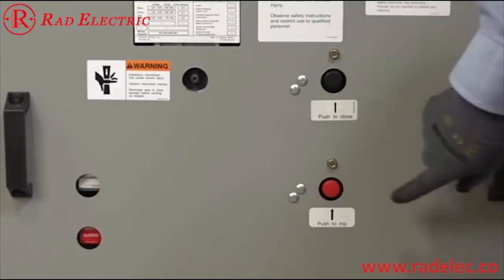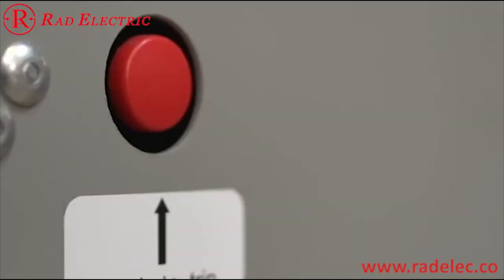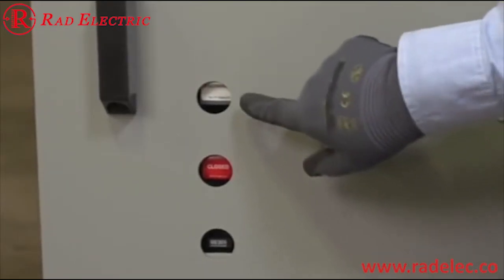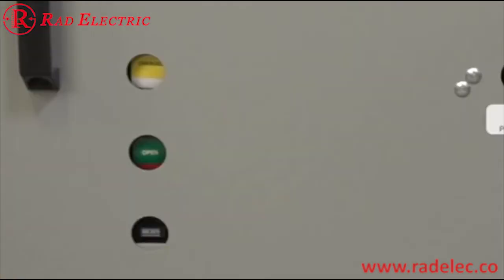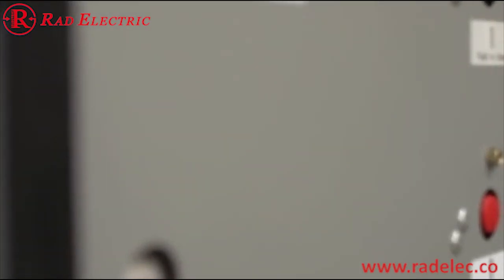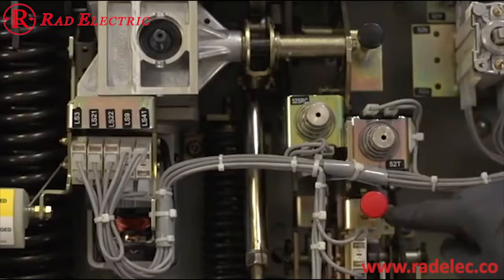This is where the charging handle is connected to charge the closing springs in the circuit breaker. These are the push to close and push to trip buttons. Both are colored according to ANSI standards. On the left side of this panel is the spring charge status indicator, which is either charged or discharged. Here is the operations counter for the circuit breaker. Remember, Siemens medium voltage circuit breakers are tested in the factory, so it's normal for a brand new circuit breaker to show 250 to 300 operations on this counter. And finally, these handles help move the circuit breaker into and out of the cell. Now, let's take a look inside. We have the trip coil, the close coil, and open and close buttons.